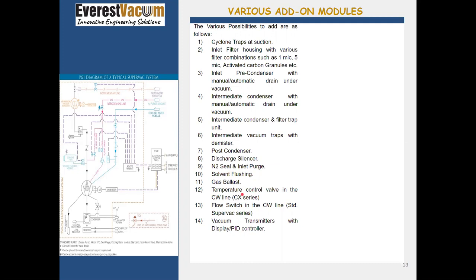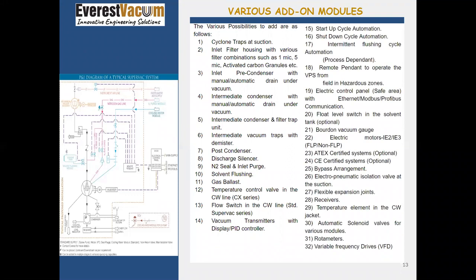Then for the CX series, that is our anti-corrosive series, we have temperature control valves. In our standard series PEEK coated pumps, there is a flow switch. It makes the system fail-proof so that the pump doesn't run dry. And then there are vacuum transmitters available with either only display or with proportional integral derivative to run the vacuum pump as per the vacuum levels required. Then there is a startup cycle and shutdown cycle. All these are pre-fed into the PLC depending upon the application. Intermittent flushing cycle as well.